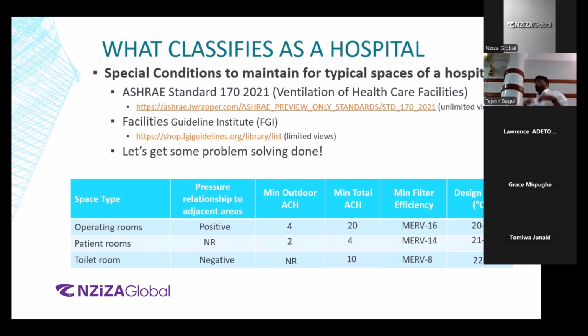All right. The total air changes per hour, we are talking about now the air changes per hour required to maintain the room at a given relative humidity and temperature conditions. If we have too much humidity outside and we are bringing unconditioned outside air indoors, the humidity in this room will rise, right? When the humidity rises, it gives rise to pathogens coming into the room. Water droplets have more capacity to carry pathogens as compared to dry air. So that is why we use the minimum total air changes per hour to take care of the building load, the heat load of it.